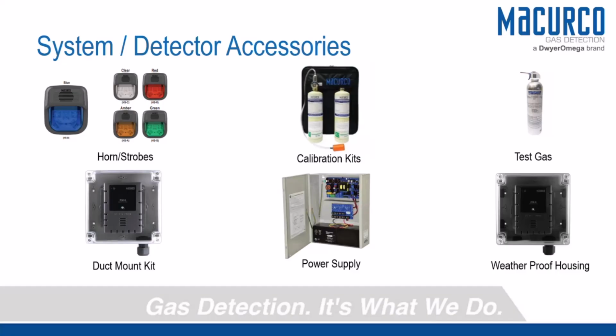One thing I want to stress with horn strobes: more gas detection is starting to be compliant with what's called temporal 4. A temporal 3 signal is for smoke, while temporal 4 is for carbon monoxide. The commercial space is starting to follow this more as well, and it pertains to gas detection as a whole, not just CO—so whether you're dealing with NO2 or combustible gas, the idea is they're looking for gas detection to use temporal 4. This is jurisdictional, not a national requirement.